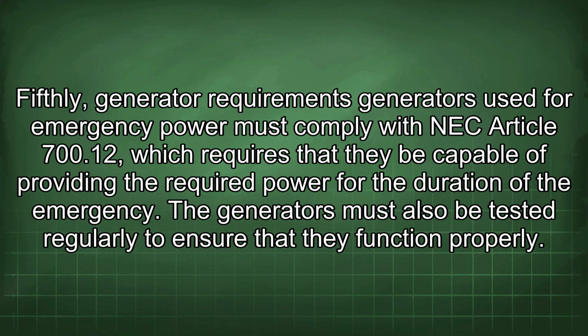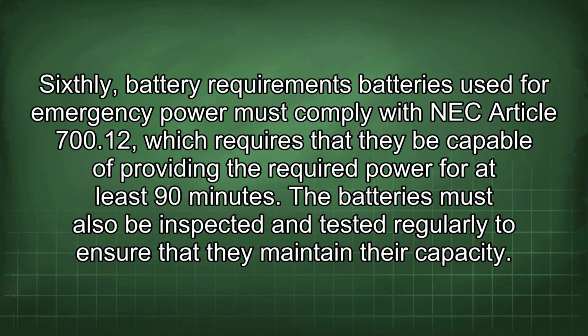Fifthly, generator requirements. Generators used for emergency power must comply with NEC Article 700.12, which requires that they be capable of providing the required power for the duration of the emergency. The generators must also be tested regularly to ensure that they function properly. Sixthly, battery requirements.